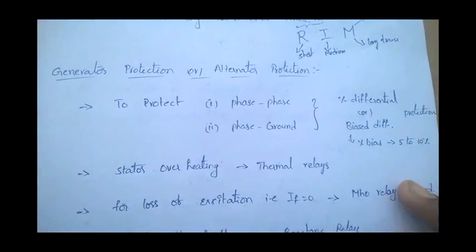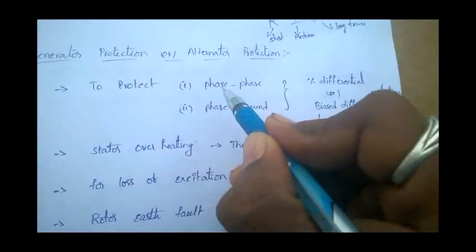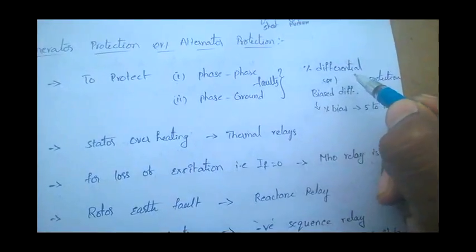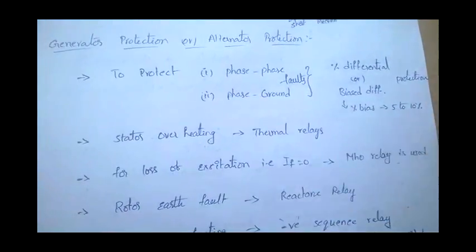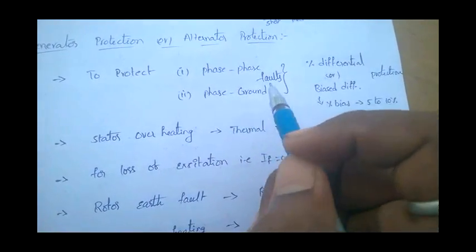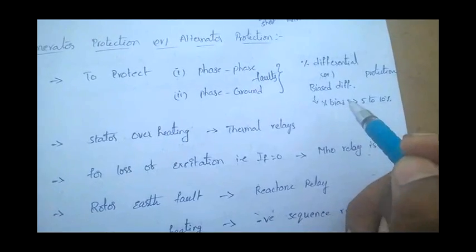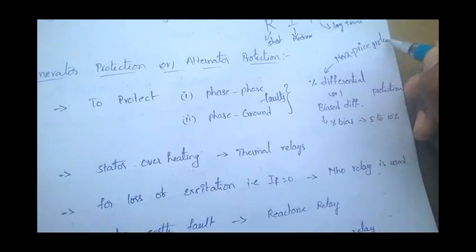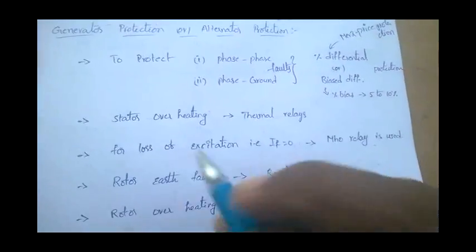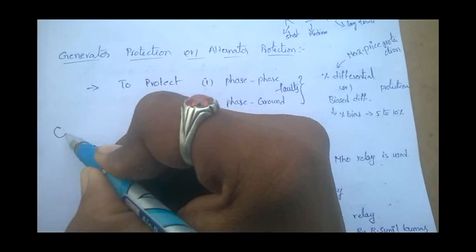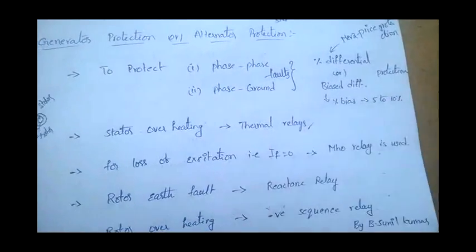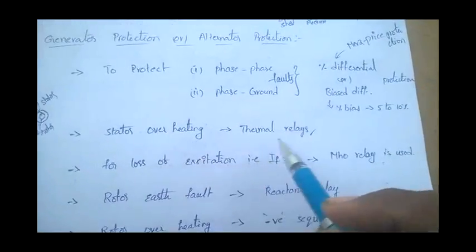Next topic: generator or alternator protection. To protect against phase-to-phase and phase-to-ground faults, percentage differential (biased differential) protection is used. This is also called Merz-Price protection. In case of stator overheating, thermal relays are used.